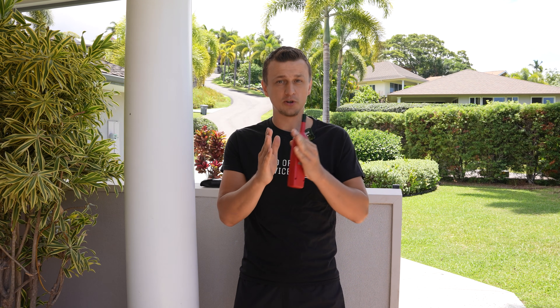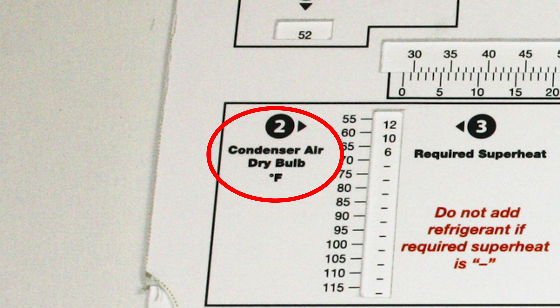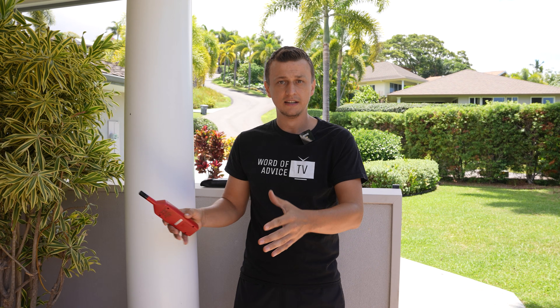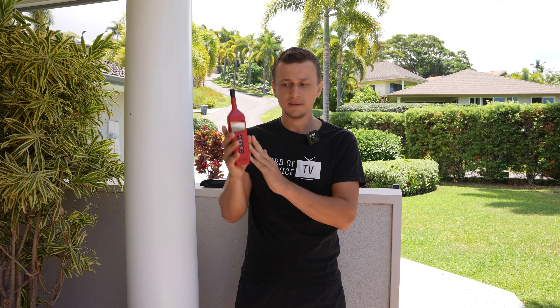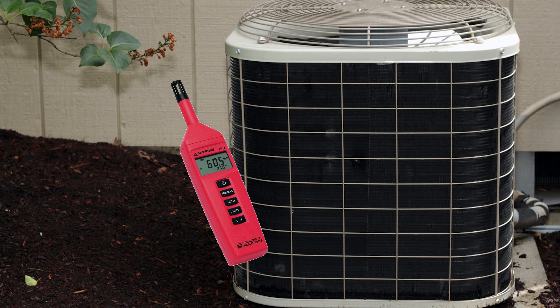If you're adding refrigerant to an air conditioner and it's asking you for the condenser dry bulb temperature, all it's asking for is the ambient temperature around the condenser unit outside. You would take a thermometer — I use a psychrometer usually — and put it on the side of the condenser where it's sucking air in, measuring the temperature going into the unit. Preferably on a shady side so the sun doesn't affect the temperature.